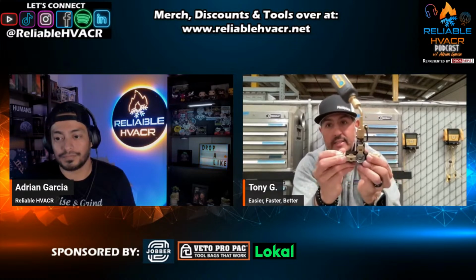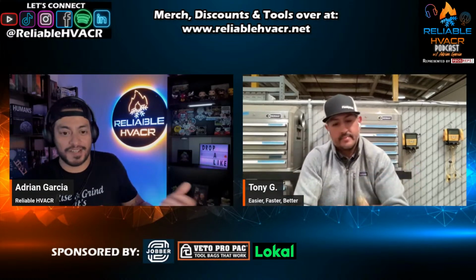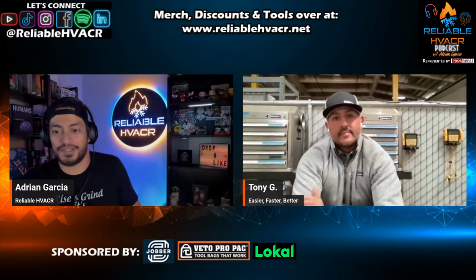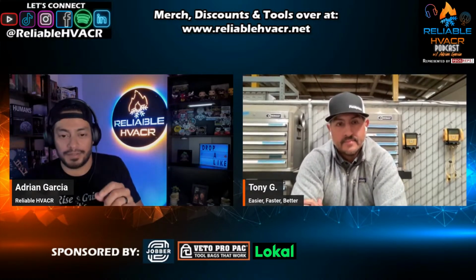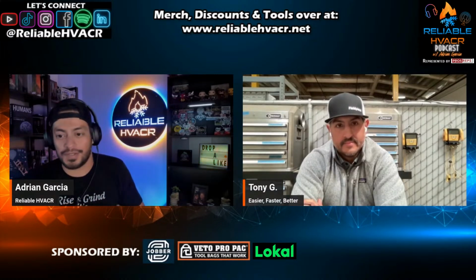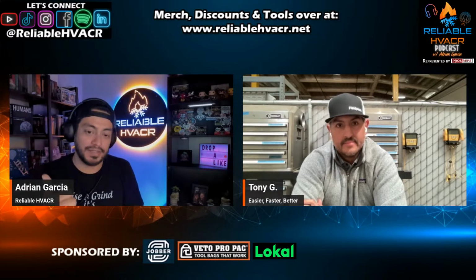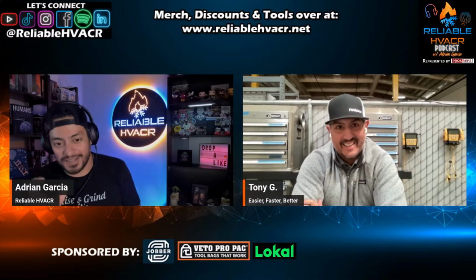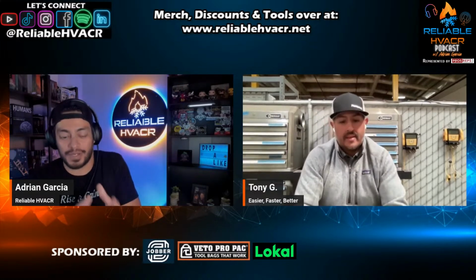It seems like it's a very simple idea, but this is the first valve core removal tool that actually has it. And I told you, it's like, why did nobody ever do this? Like, the sight glass was a big one for me, because how many times, and everybody makes a joke about it, like, did you get the valve core? Did you get that Schrader out, right? And there are little tips and tricks, pinch off, make the puller tighter, do this, do that. I've had to literally pop them out by opening the valve to get the pressure to pop it out, because sometimes I don't know where it's stuck at. There's tons and tons of stuff where if you just had a sight glass, you could see what the hell was going on. And then the valve that you said on the other side of the micron gauge, that's another thing.